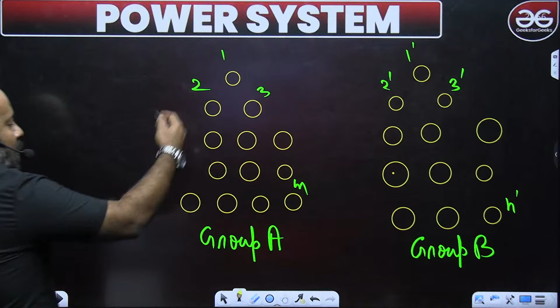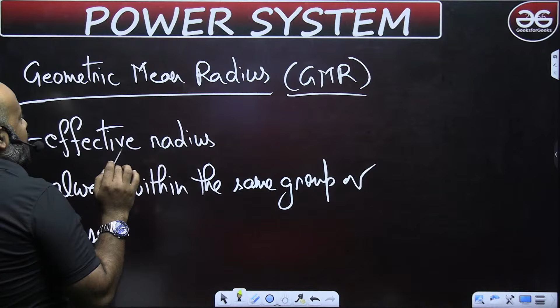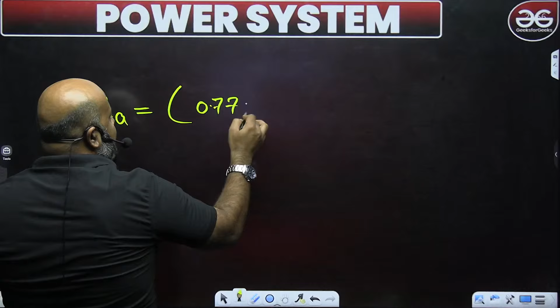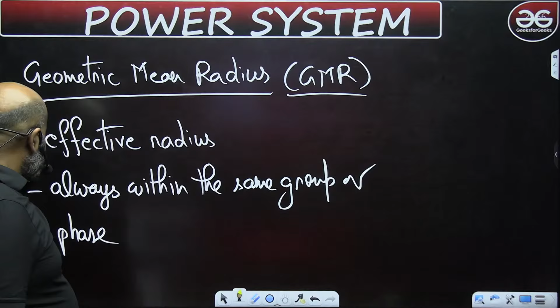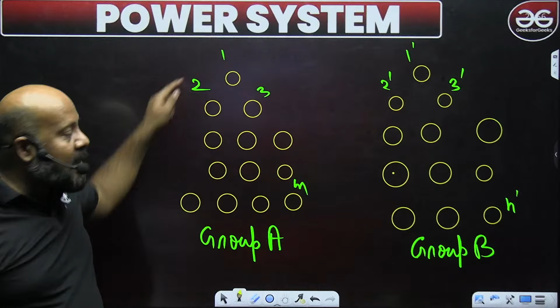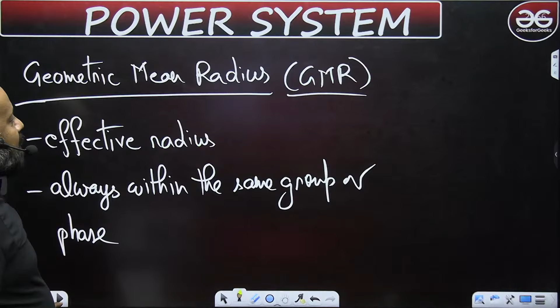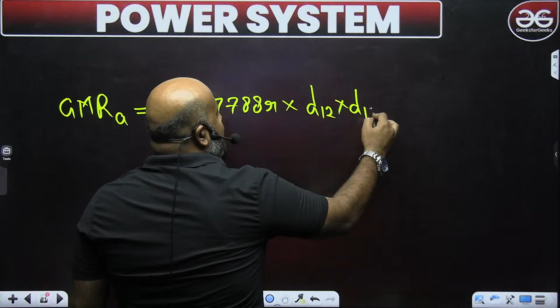Suppose I am writing it for GMR of group A. First I go for conductor number 1: its effective radius is 0.7788R multiplied by the distance between conductor number 1 and all other conductors in this group - distance between 1 and 2, 1 and 3, 1 and 4, up to 1 and M.